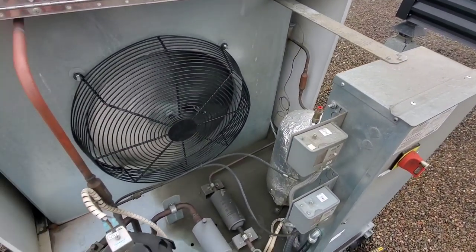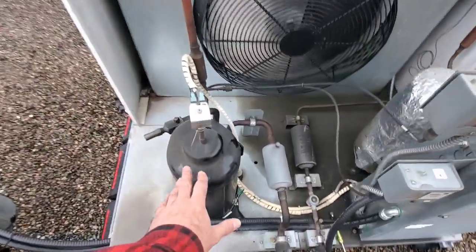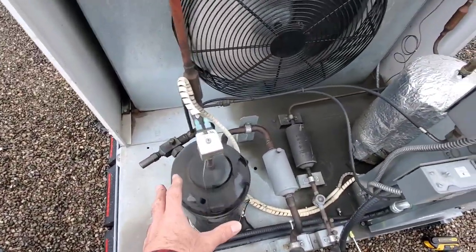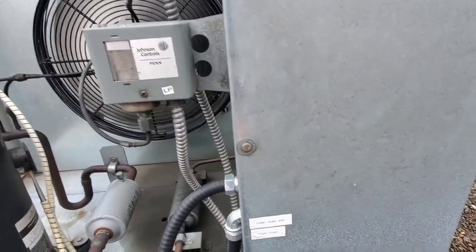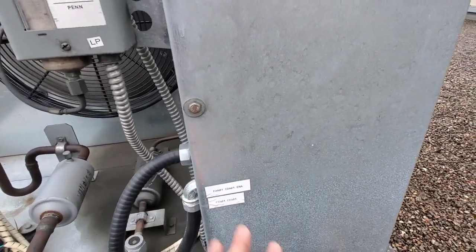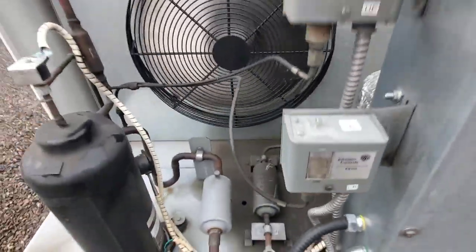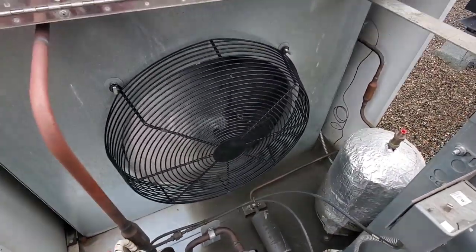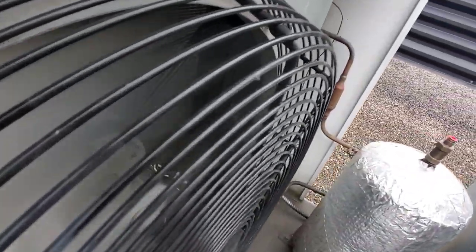We have this air cooled condensing unit. It's got a scroll compressor — a digital scroll. Inside here is a superheat controller which controls the EEV downstairs, the electronic expansion valve. You did see the condenser fan motor struggle to start up. I believe it's the capacitor that's causing this problem, but the capacitor is tucked back in there.